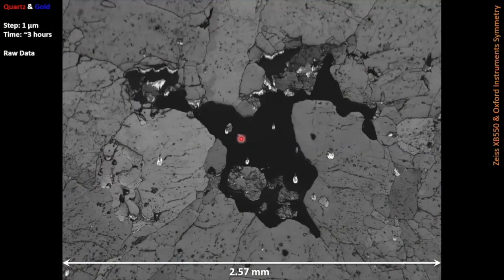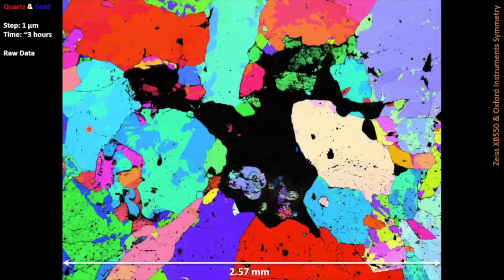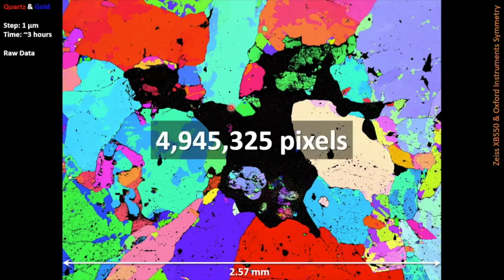If we change to the band contrast image, you can see where we're getting good signal versus bad signal — there's a porous area in the middle illustrated by black, where we don't get the signal, and gold grains in amongst the quartz around the outside. Changing to what we call an IPF map — an inverse pole figure map — this allows you to see the different orientations: each color represents a different orientation of the grains. Even where all the quartz is dominant in the phase map, it's still not oriented all in the same direction, so we have a natural crystalline fabric that hasn't been strongly affected by stresses. This is almost a 5-million-pixel map — a lot of data points generated really quickly.